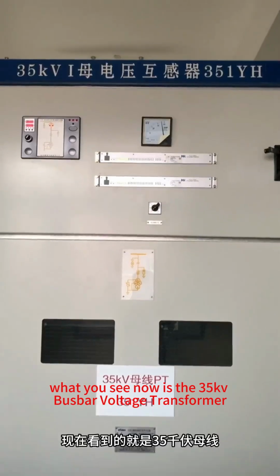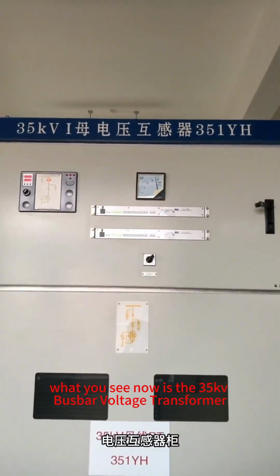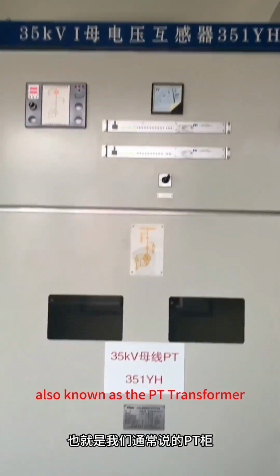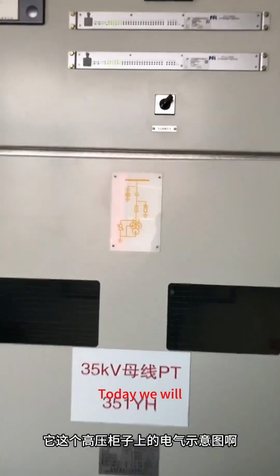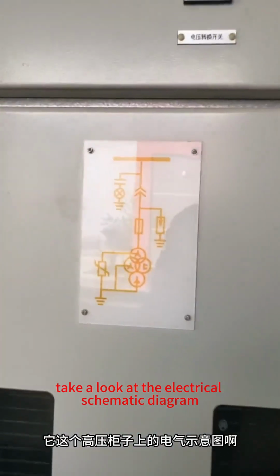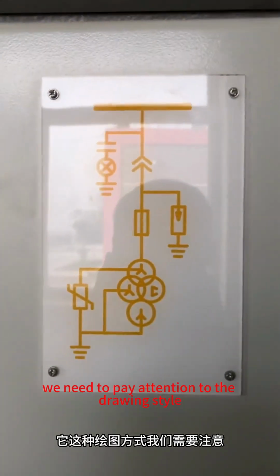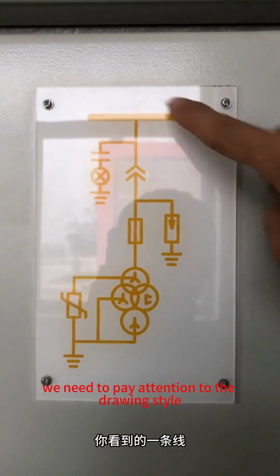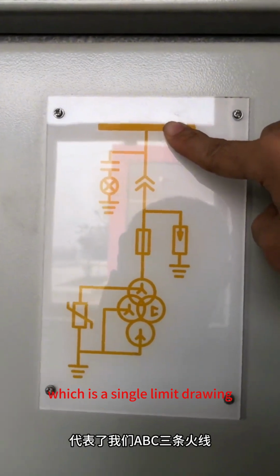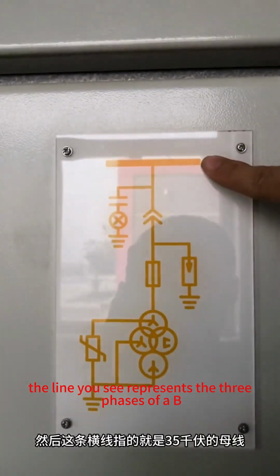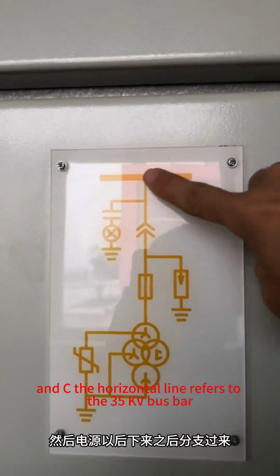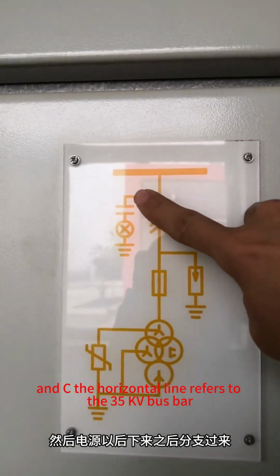What you see now is the 35 kV busbar voltage transformer, also known as the PT transformer. Today, we will take a look at the electrical schematic diagram on this high voltage cabinet. We need to pay attention to the drawing style, which is a single line drawing. The lines you see represent the three phases A, B, and C. The horizontal line refers to the 35 kV busbar.